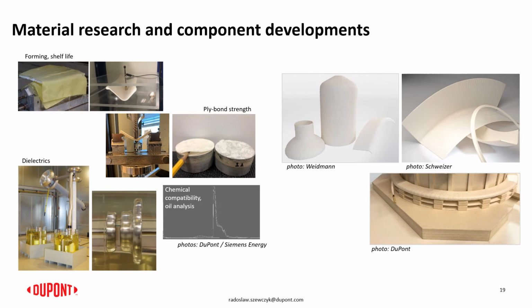We are working on increasing the size of the high density board for larger and larger components, which requires lots of characterization for the mechanical performance, for the dielectric performance of the new grades. If there is a need for the laminated board, like for the clamping plates, this requires thorough evaluation for the dielectric strength, not only for the press board itself, but also for the laminated board.